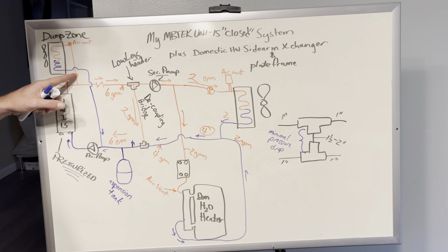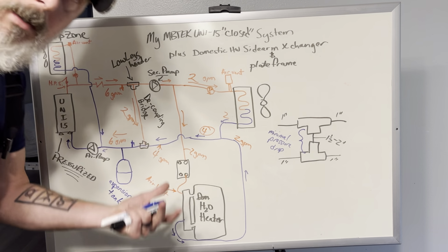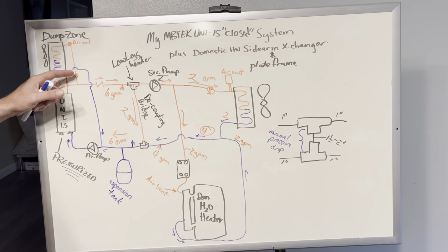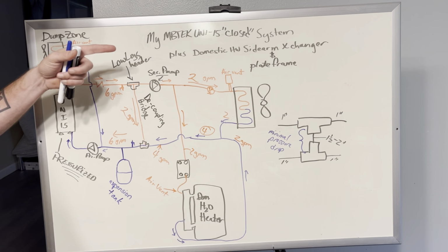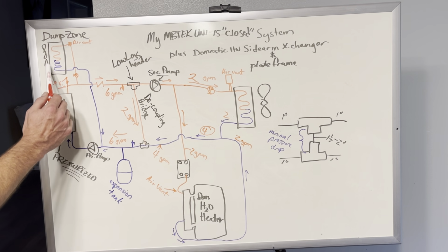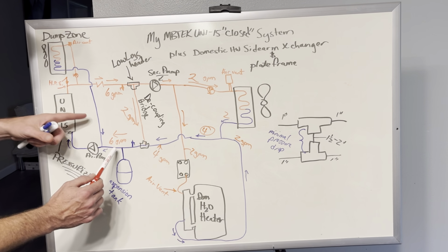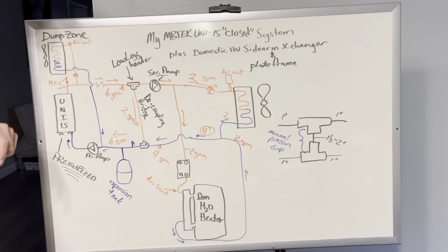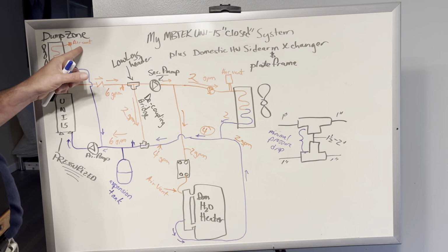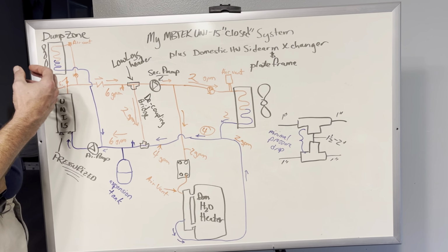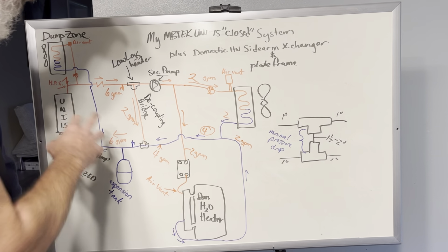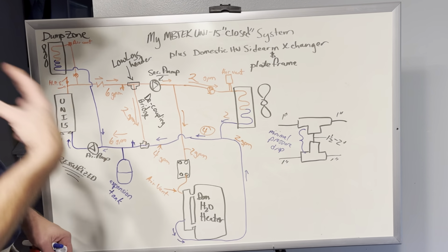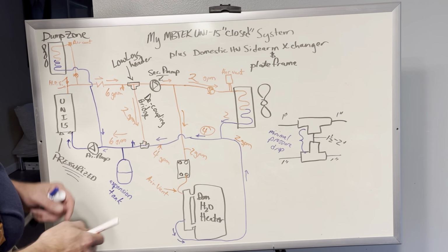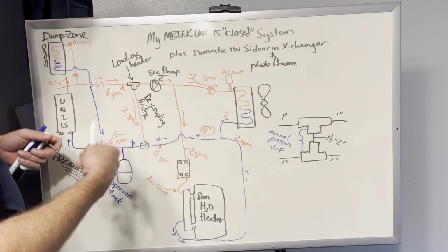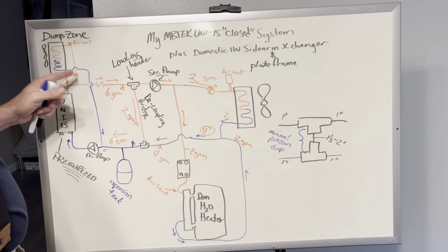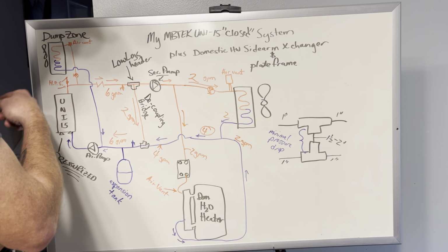So basically this valve is automated. When the thermostat in the building says I'm cold, it will open that valve, turn that blower on, and put heat in the building. And so that return water comes down and marries with this return water to go back into the boiler. This is the dump zone though. Its most important job is if I have a high temp situation, where the water's just gotten hot for whatever reason, my failure. If I have electricity and everything's working great, and the thermostats pick up on the fact that the water's gotten so hot, it will bring this heat on. It'll turn the fan on, open the valve, and let it go.